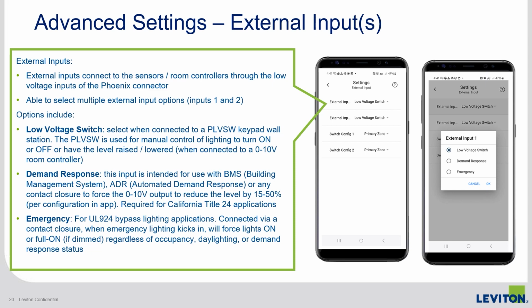Select demand response for California Title 24 applications when connected to a BMS, ADR, or any contact closure where lighting output needs to be reduced when a signal is received. Levels can be programmed to reduce anywhere from 15 to 50% when a signal is received. Lastly, we have emergency. This is the opposite action to demand response. When connected to BMS emergency system, a signal is received through the dry contact and lighting will go full on regardless of dim level or on or off state.